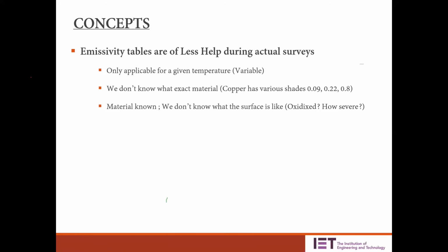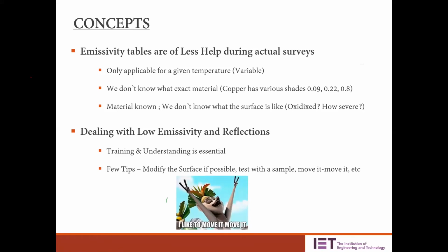So if we have low emissivity and high reflections, a few tips would be to modify the surface if possible, if it is safe to touch, and test with a sample. If you have a sample, there are methods to measure the actual emissivity.